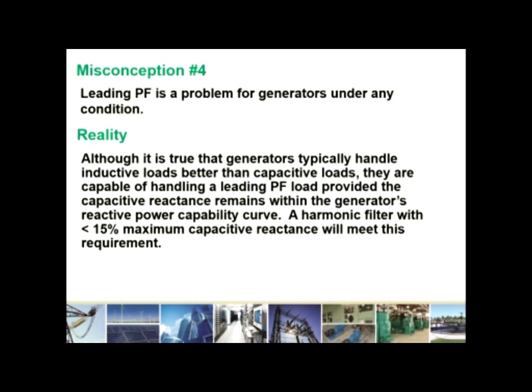So misconception number 4 is that leading power factor is a problem for generators under any condition. Whereas in reality, although it is true that generators typically handle inductive loads better than capacitive loads, they are capable of handling a leading power factor load provided the capacitive reactance remains within the generator's reactive power capability curve. A harmonic filter with less than 15% maximum capacitive reactive power will meet this requirement.